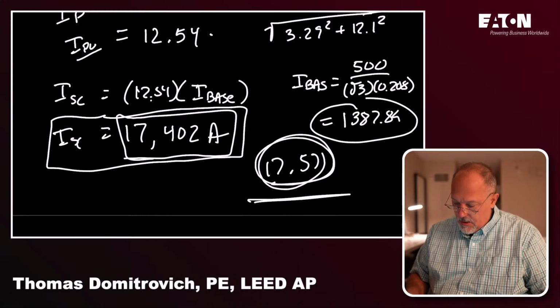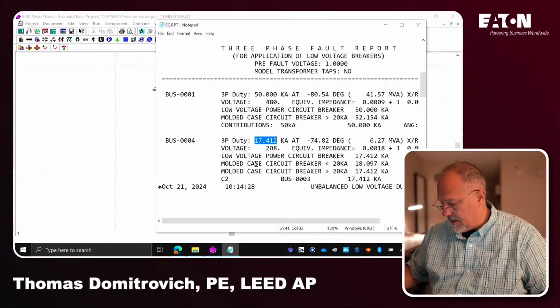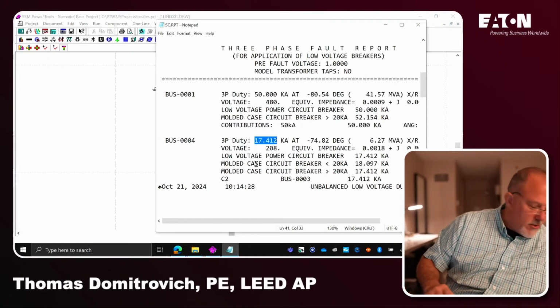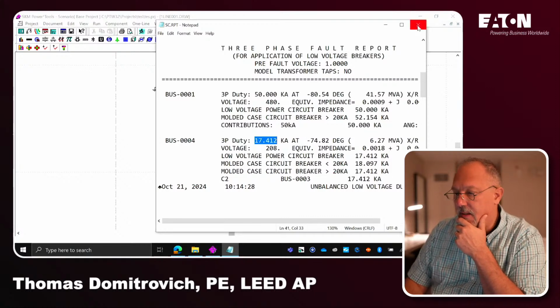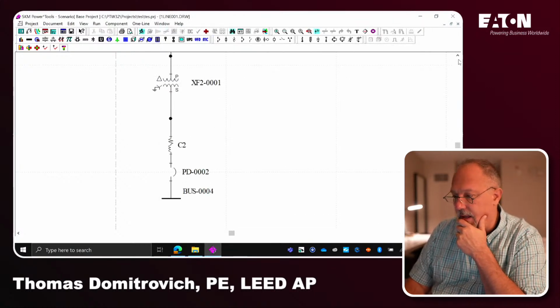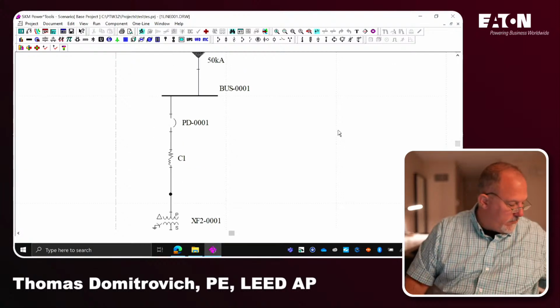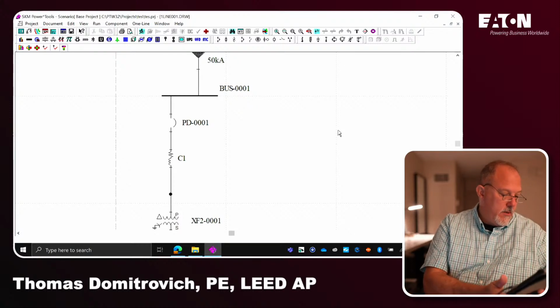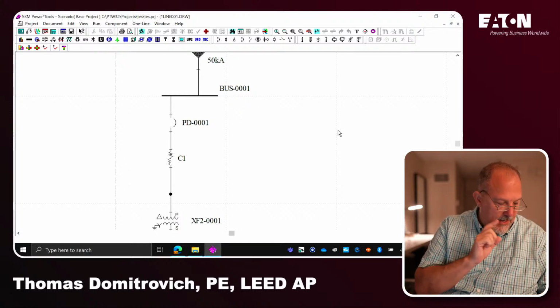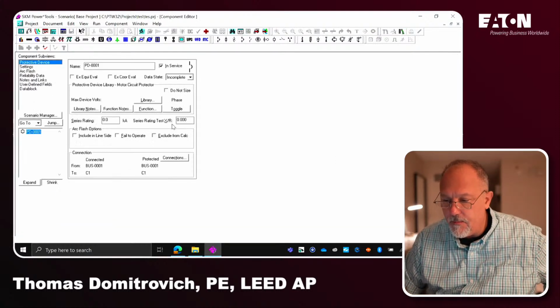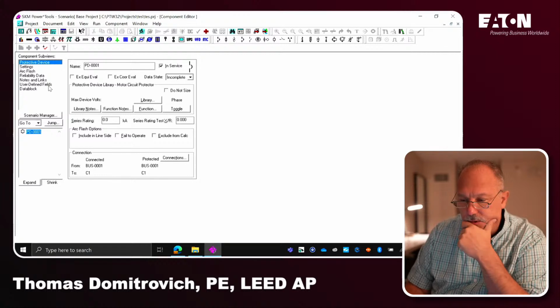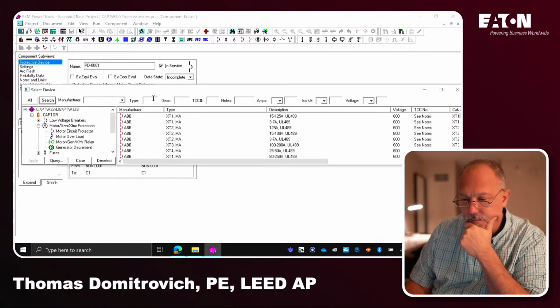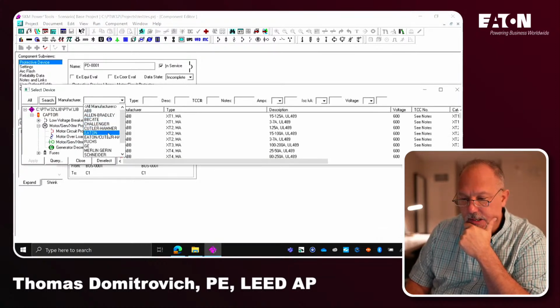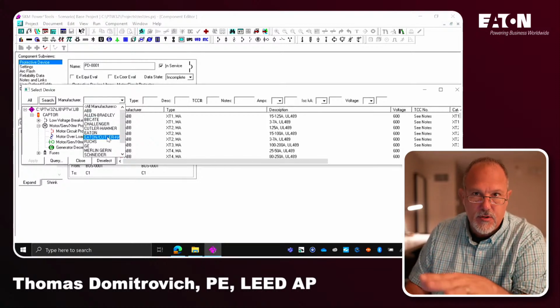So now comes the fun part. Now I've got to pick the circuit breakers. So we know our numbers look good. What was the circuit breaker? It's 800 amp. So we have to pick an 800 amp breaker at the top. So if we go to library, now remember, this is the only way to get SKM to correctly work. You have to do this.